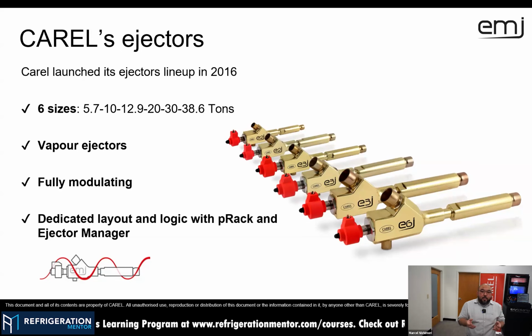And a positive side effect is that we can use all this energy that we are expending the CO2 throughout the HPV or the ejector to make a small compression from medium temperature refrigerant flow, okay? And these logics are controlled by two different types of controllers. We can use the pRack, our standard rack controller for transcritical solutions, but CAREL is also bringing to the market a new product called the Ejector Manager. So imagine a dedicated controller, a standalone, that you could use to drive CAREL's ejectors, PWM ejectors, and make it integrated to any type of control. So it could be CAREL, could be any other brand of your preferred compressor control logics, and it will be working seamlessly with all these types of technology. Okay.